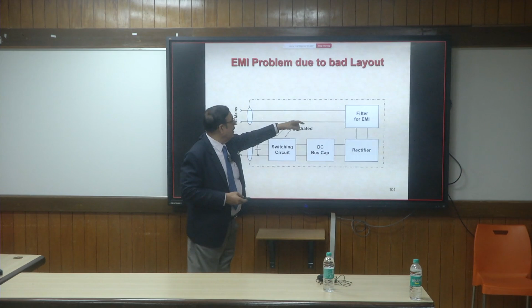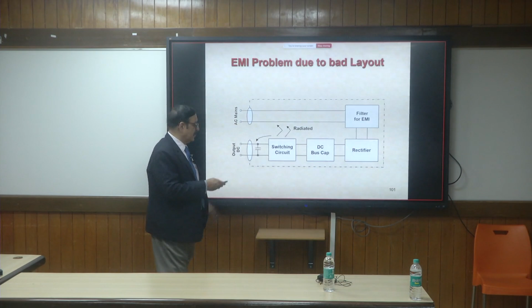The filter should not be there. The filter should be here, physically at the entry point of the AC mains. Then whatever wiring you have inside, whatever it picks up cannot send it back to the mains. So your system will not be sending anything out on the input side. Similarly, you can have filters on the output side also.